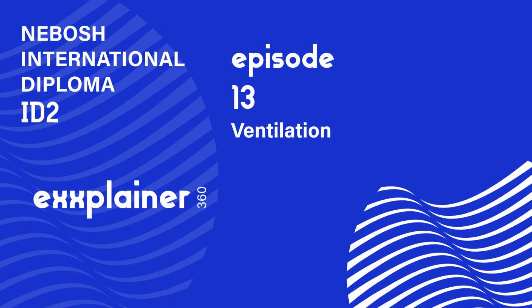Got it. Okay, let's start with the simpler sounding one: dilution ventilation, DV. Right. The basic idea is, well, simple. You don't try to capture the contaminant right where it's made. You just bring in enough fresh air to dilute it down to an acceptable level. And you measure that with air changes per hour, ACH. Exactly, ACH. How many times per hour does the entire volume of air in the room get replaced?